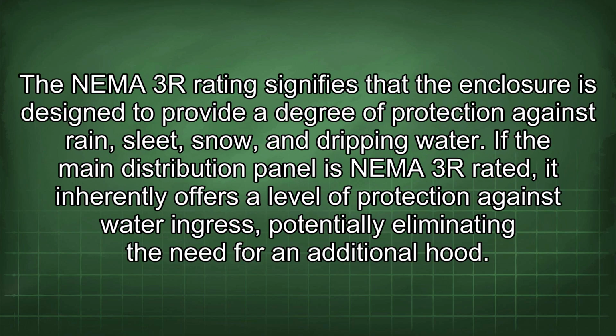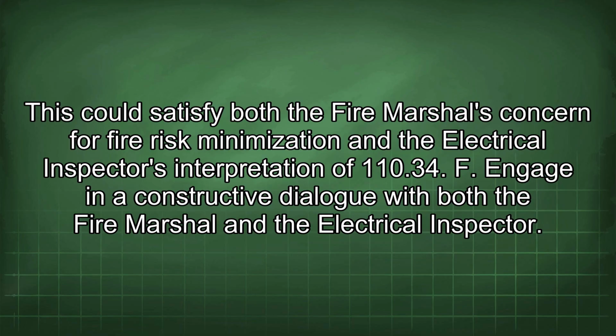The NEMA 3R rating signifies that the enclosure is designed to provide a degree of protection against rain, sleet, snow, and dripping water. If the main distribution panel is NEMA 3R rated, it inherently offers a level of protection against water ingress, potentially eliminating the need for an additional hood. This could satisfy both the fire marshal's concern for fire risk minimization and the electrical inspector's interpretation of 110.34.F.